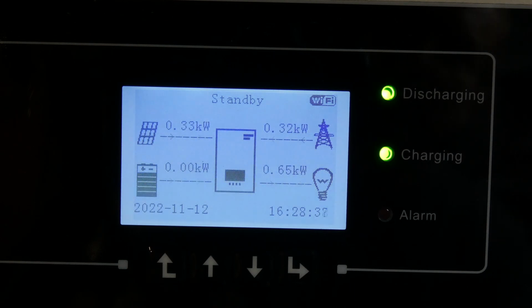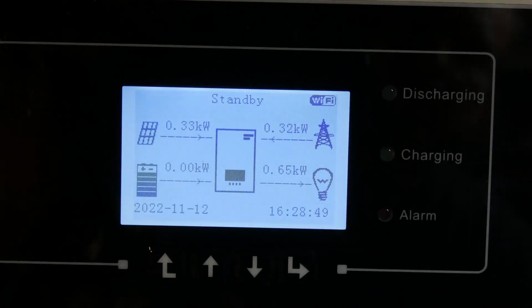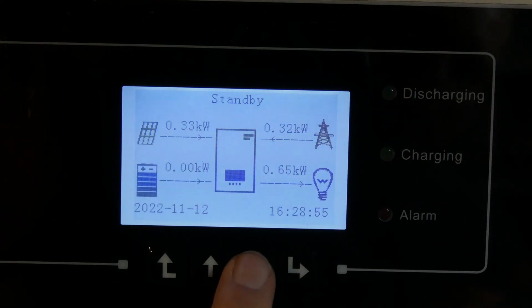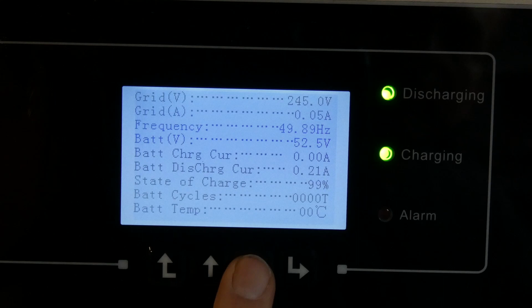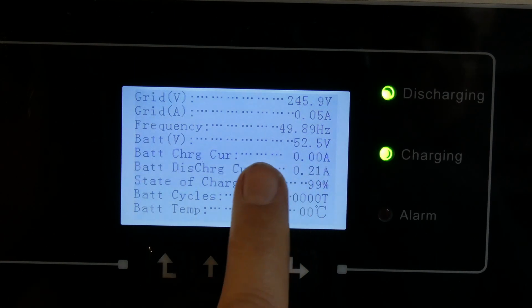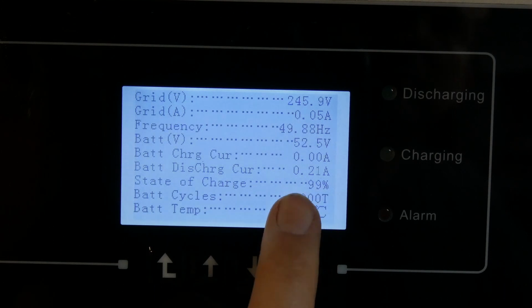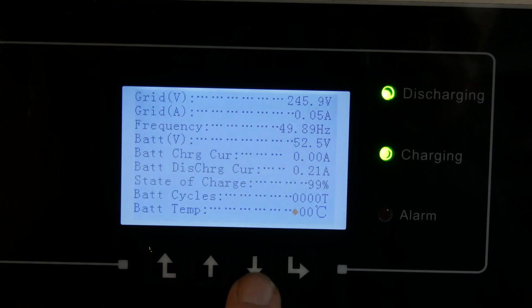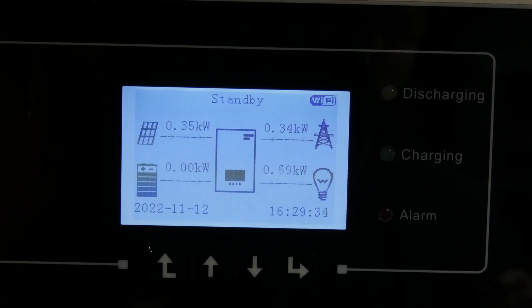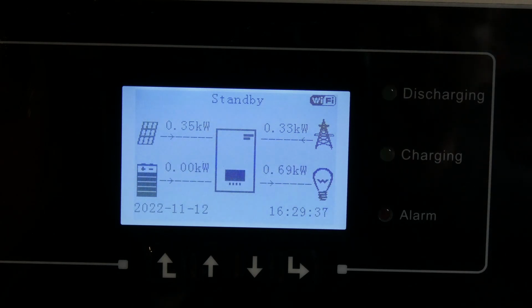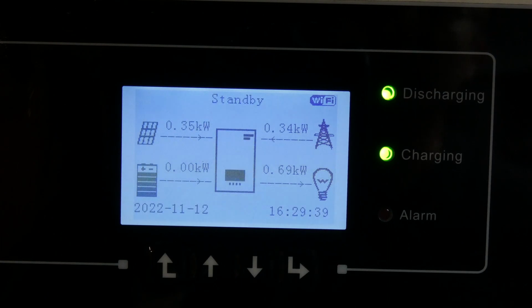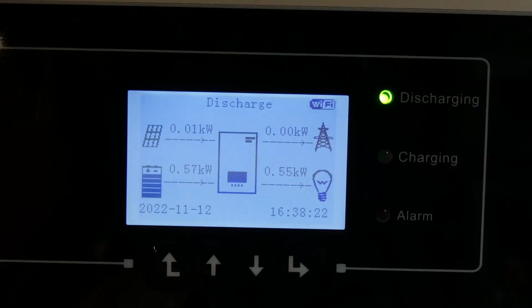The question is, will it start pulling from the battery? So it's going into standby mode now. If we look at the settings on here, we can see battery voltage 52.5 volts, charge current is 0, discharge current 0.2, state of charge is 99%. That's actually just the DIYBMS current monitor reporting that. At the minute it's not charging or discharging, so I need to go away and have a look what that means. A few minutes later...